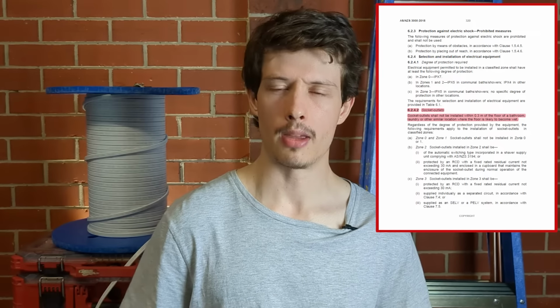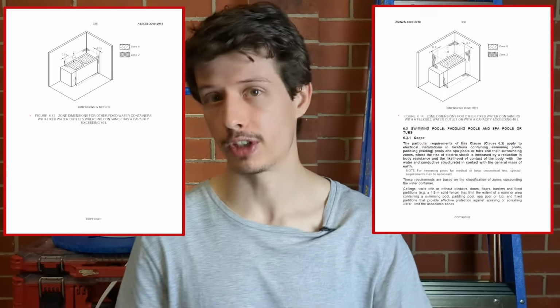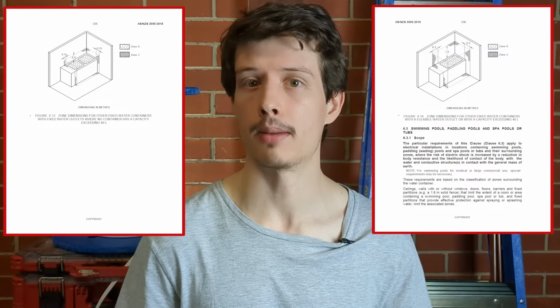Clause 6.2.4.2 gives you the minimum requirement that power points need to be above the floor in bathrooms and laundries, which is 300 mil. Usually when we're roughing in cables for bathrooms, we're not locating power points near the floor. It's usually above the vanity. There are also rules for how far power points can go near sinks, showers and baths. I'll quickly go over the sink rules, which in the AS3000 are referred to as fixed water containers. Figures 6.13 and 6.14 give you the exact dimensions for power points in terms of their proximity to those fixed water containers.